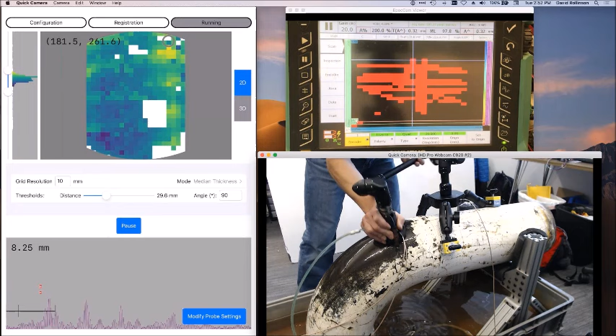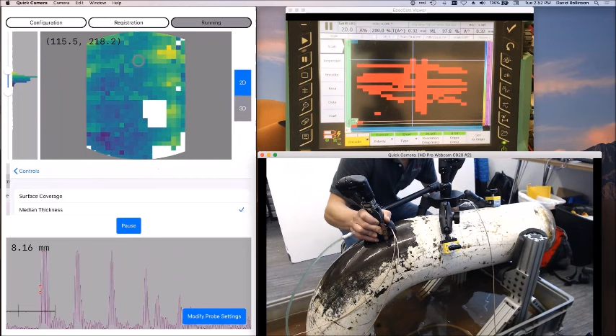And then the next thing I want to demonstrate with this is basically the ability to do variable density on that data. So I'm running on a 10mm grid here. If I wanted to say, look at that low spot in the bottom left corner there, I can increase that density down to 2mm, and I can go do that in more detail.